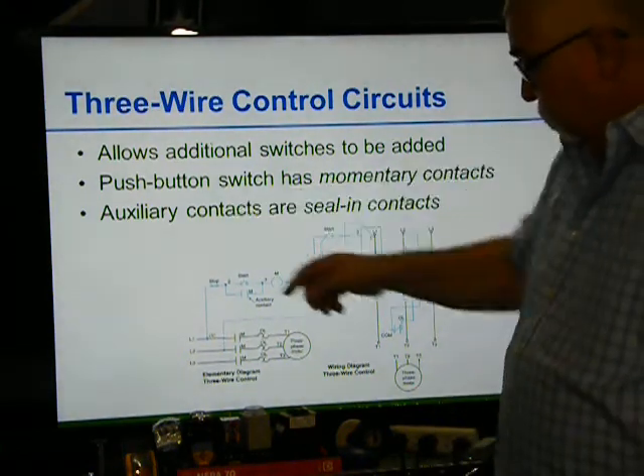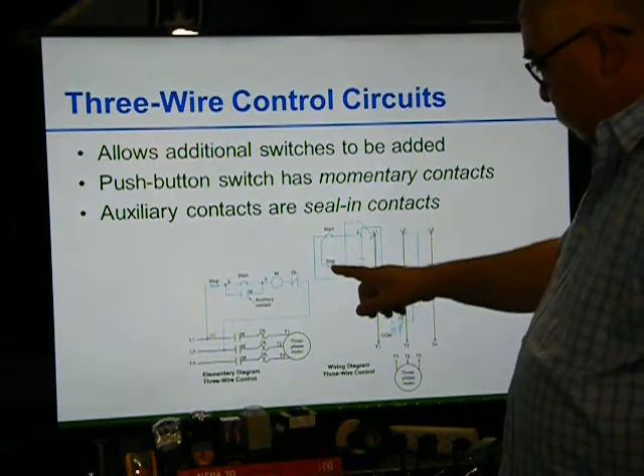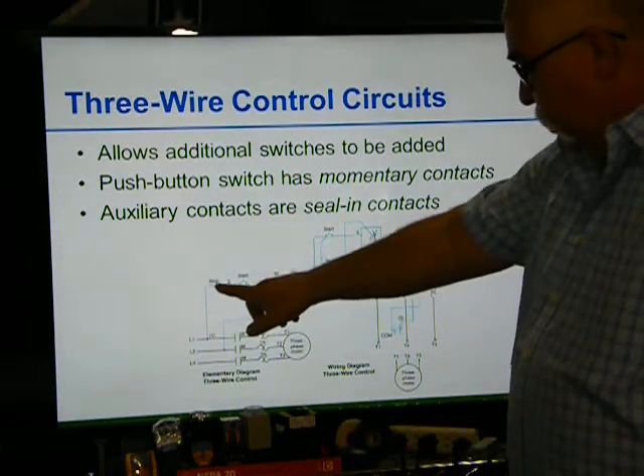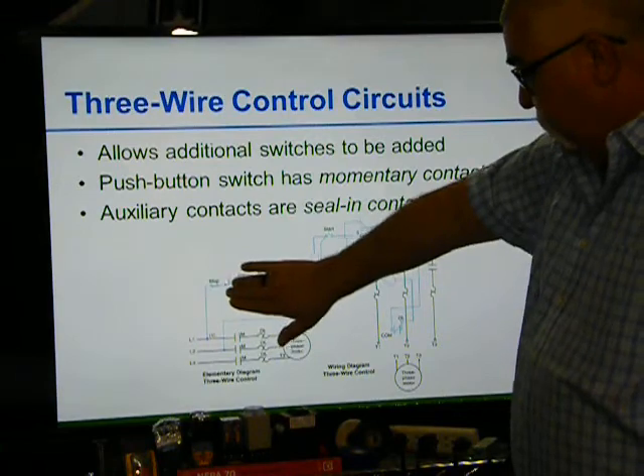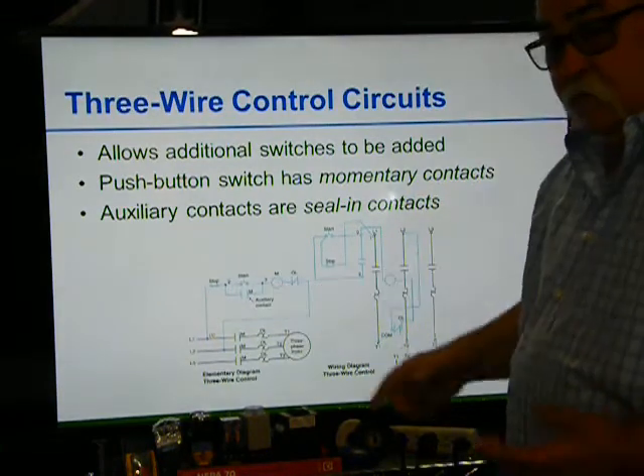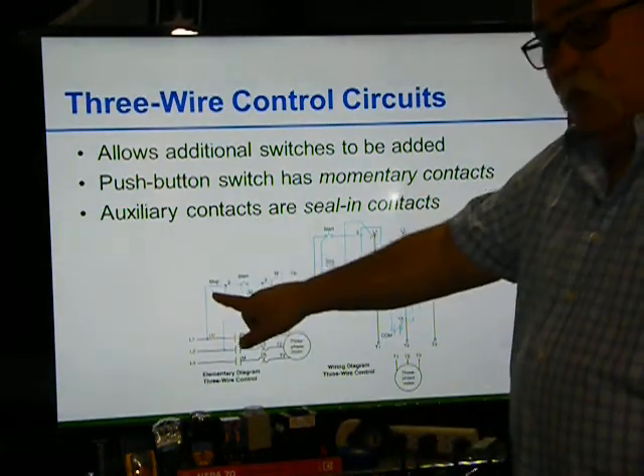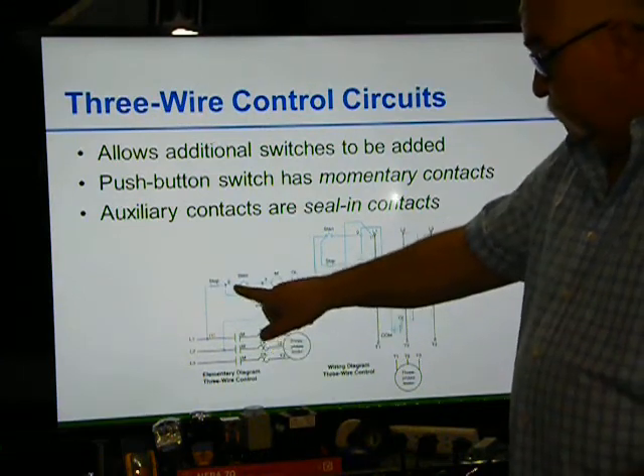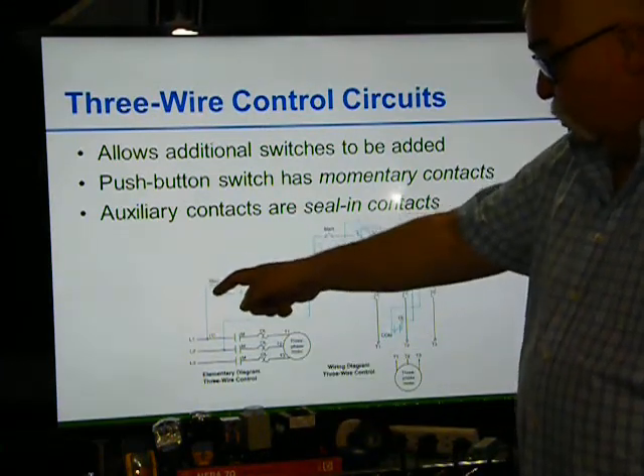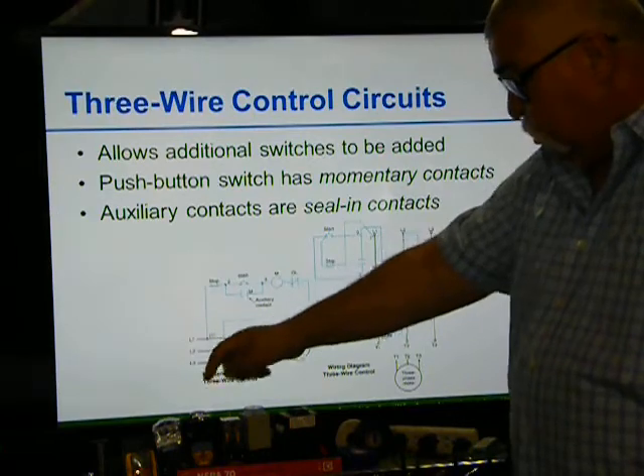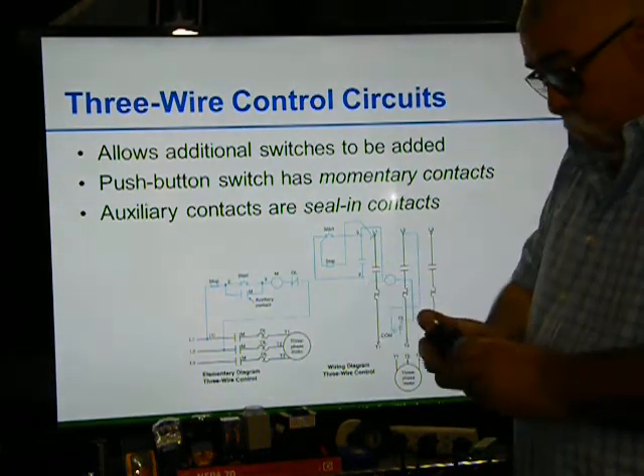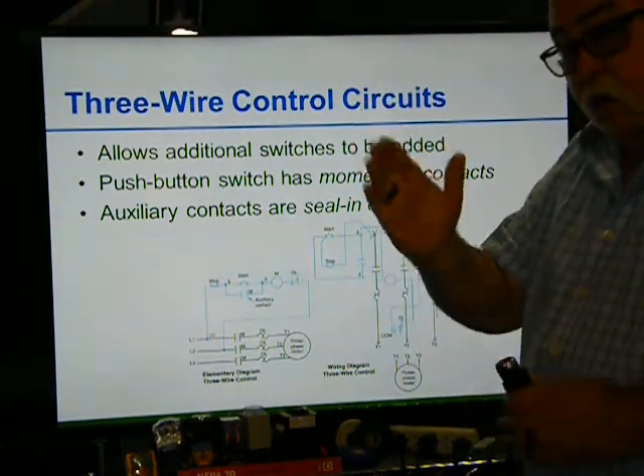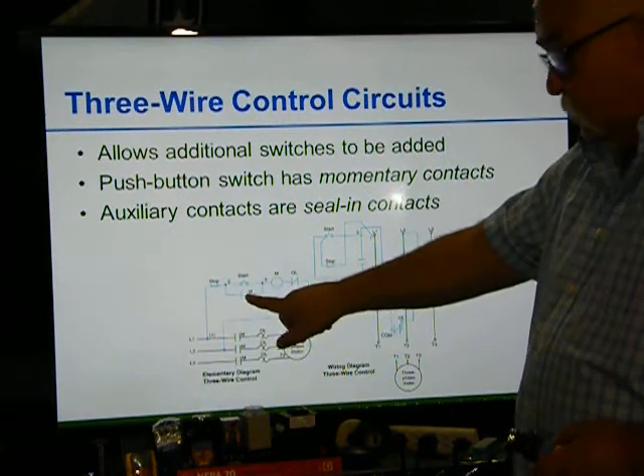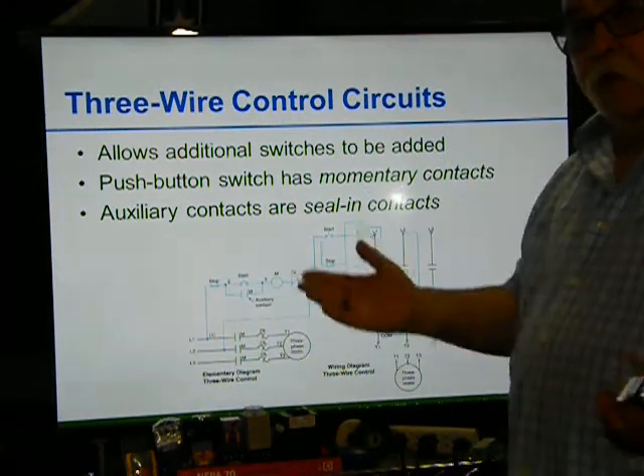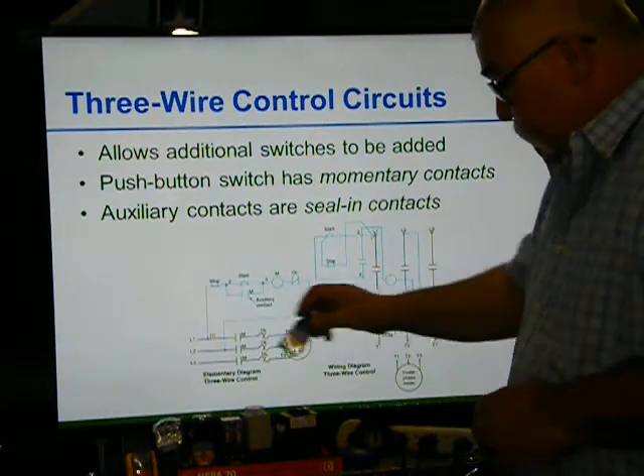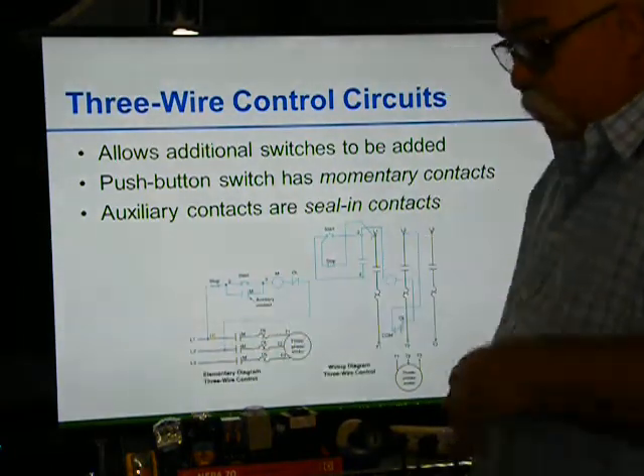Okay, when I hit the stop button, you can see right here, now from here down to here, voltage is removed because I'm opening the switch. The stop opens it, the start closes it. So as soon as I push the stop button in, it breaks that contact, it loses the voltage. This sees that voltage is gone, and the contact opens. Okay.